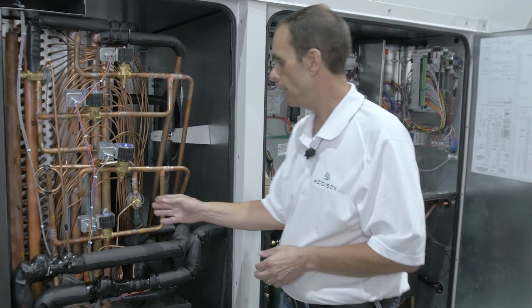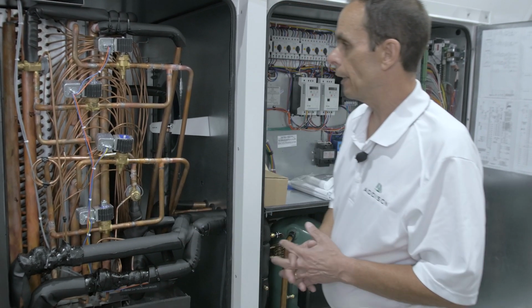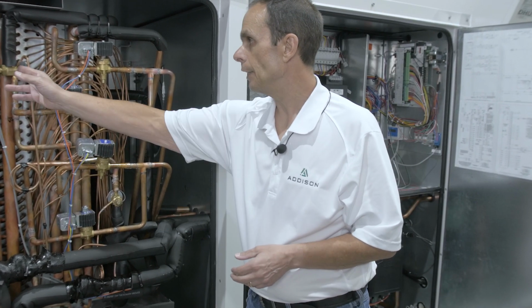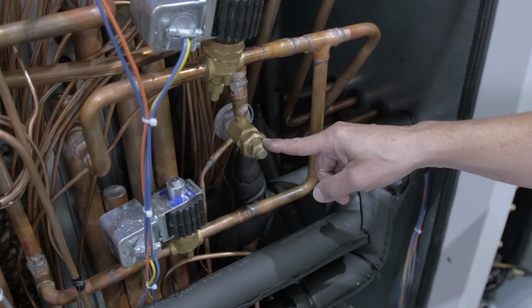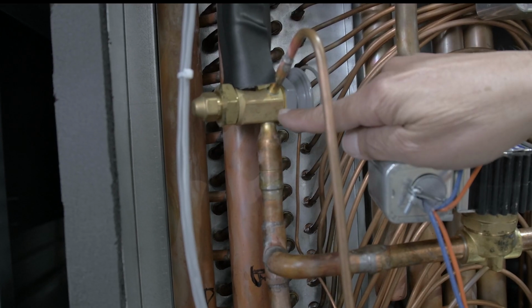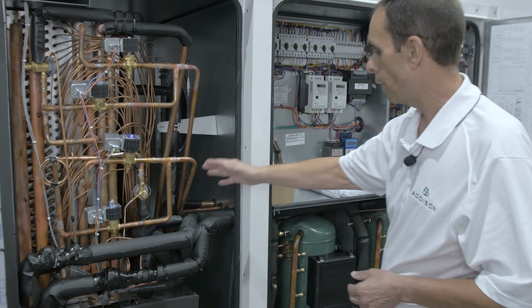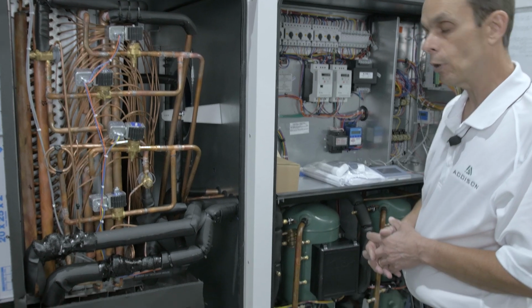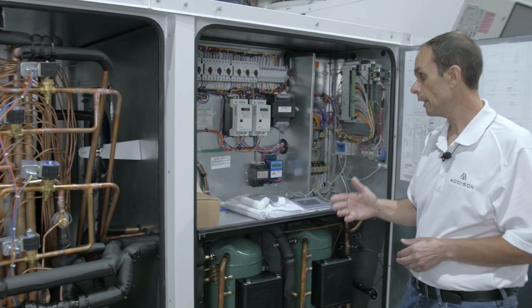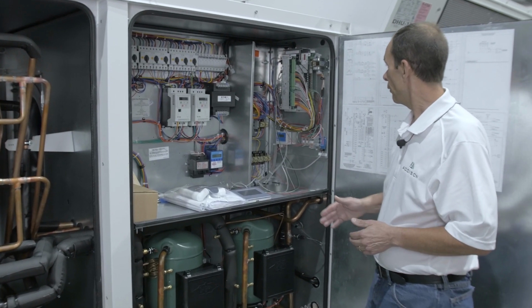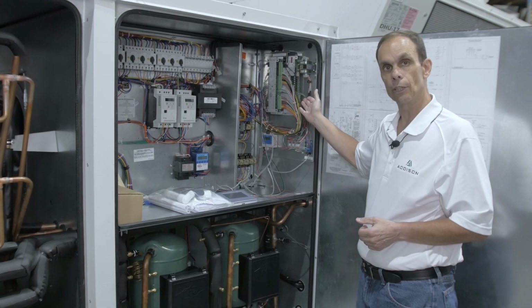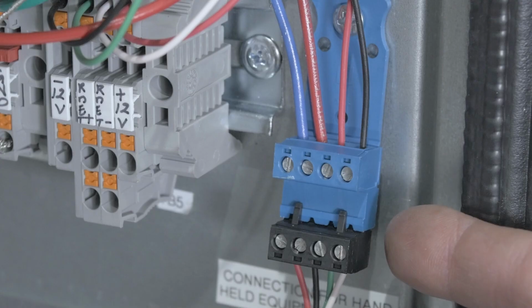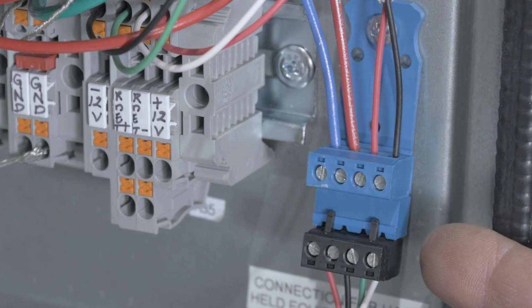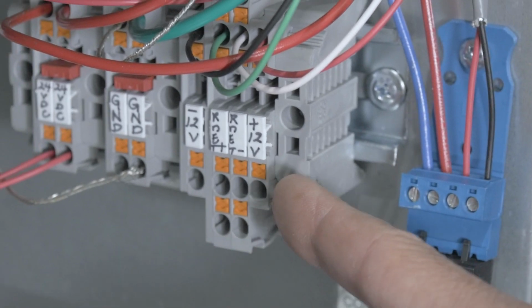So now you have your TXVs that are in here, and again, stage 1, stage 2, TXV for stage 1, TXV valve for stage 2. Now we're going to move over to our other compartment here where our controls are. So in our control compartment here, you're going to have your ALC controller with expander board. Here's your blue plug for your equipment touch. Here's your terminal block number 5.